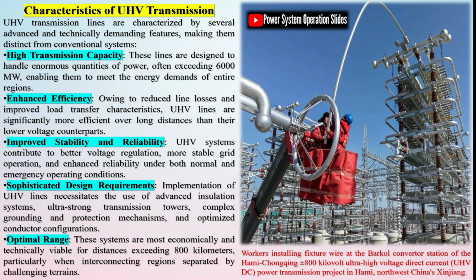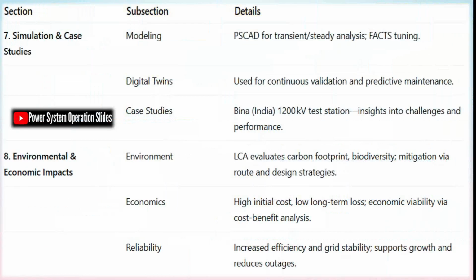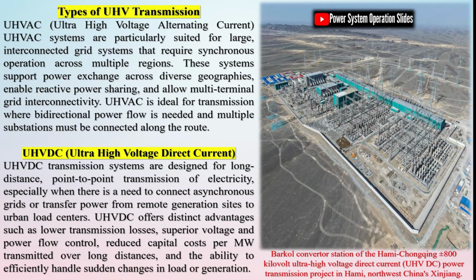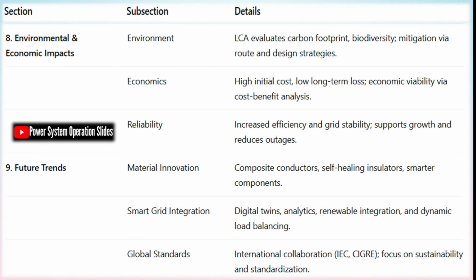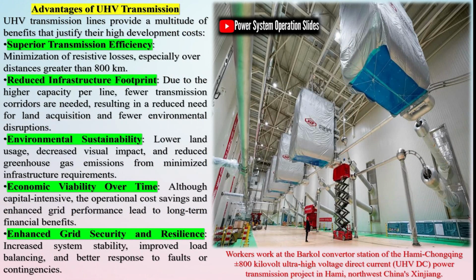UHV direct current (UHV DC) is often chosen for ultra-long distance transmission, and it interconnects networks that might be asynchronous or operate at different frequencies. Converter stations: these systems require sophisticated converter stations at both ends. One station rectifies AC power to DC for efficient transmission, while the other inverts the DC back to AC prior to distribution. Advantages: with lower reactive losses and enhanced control over power flow, UHV DC is particularly effective in reducing transmission losses over vast expanses.